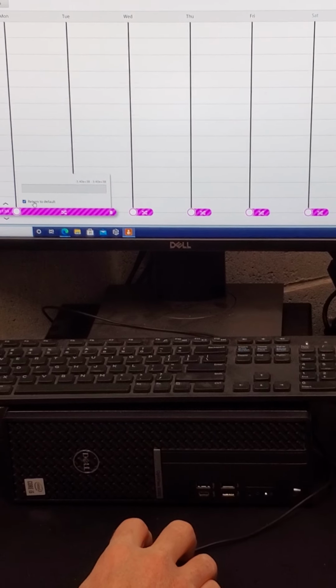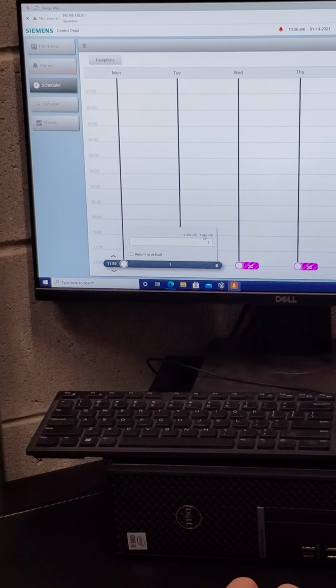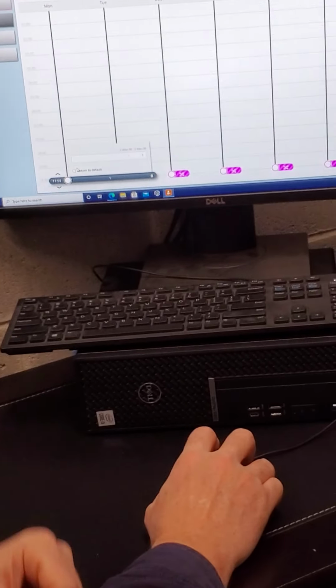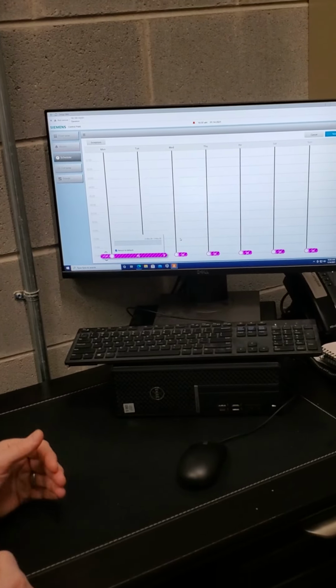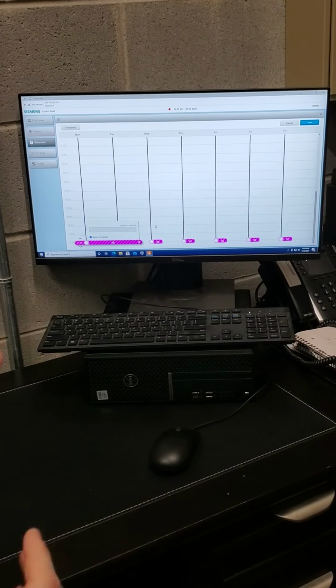Those can be changed. It could be, take that out of there. We could go to a different state instead of returning to default. So if we wanted to command something on and command it back off, we would know those 2 states. Being that this is a schedule for a DOAS unit, there's usually a lot of states to consider: occupied, unoccupied, auto, off, depending on the controller.